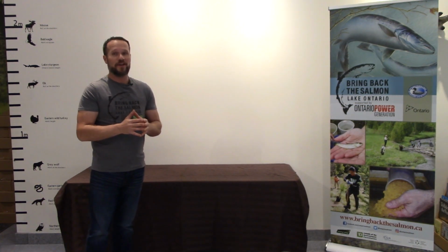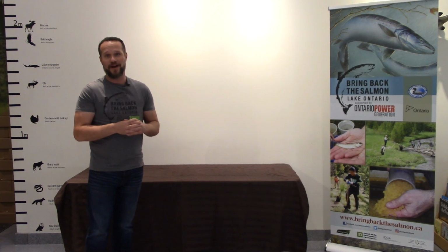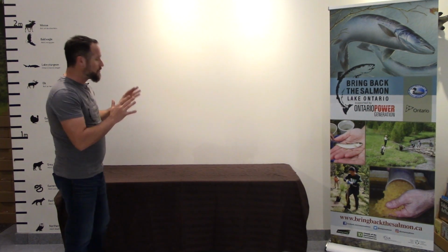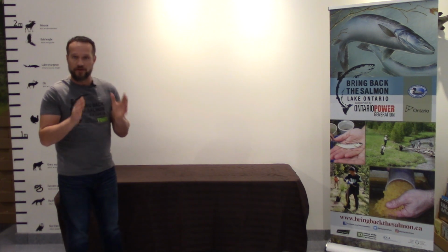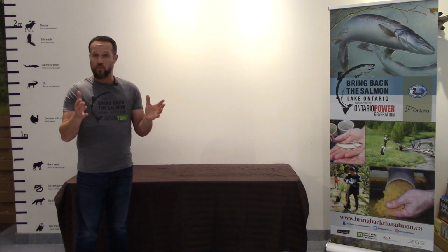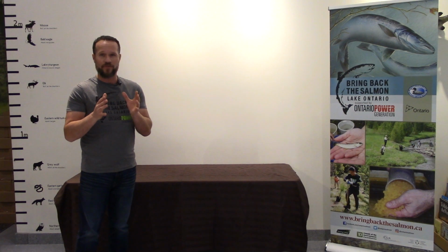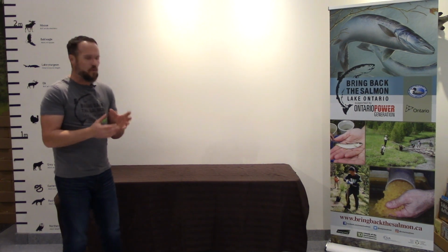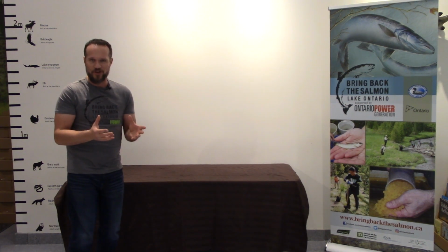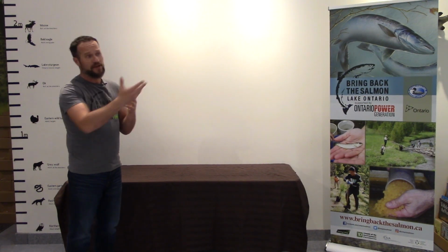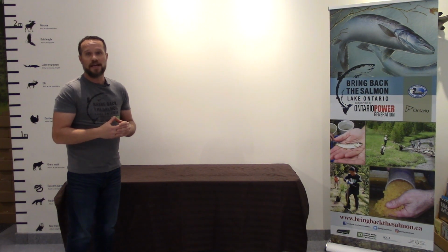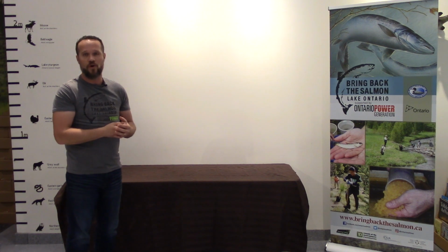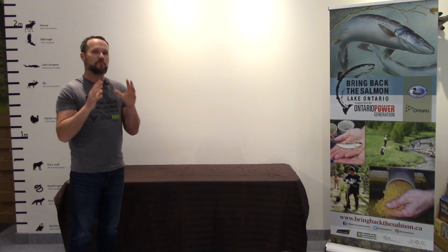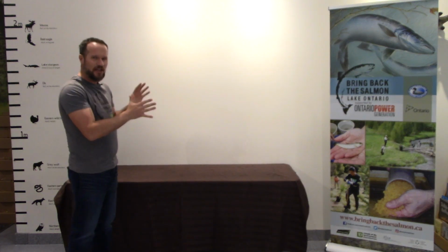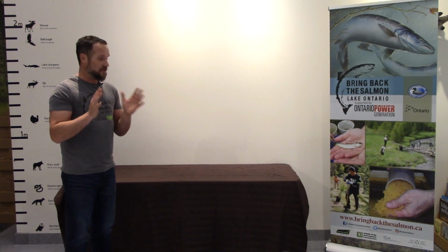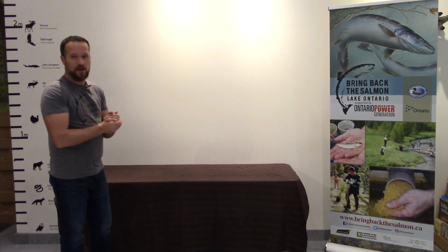First thing we want to think about is where we're going to put our classroom hatchery equipment. We want a spot that is away from any exterior doors, windows, or heat sources. That's just because we want efficiency of the unit. We don't want it being warmed up by sunlight or a heat source while the chiller is trying to cool our water down. We also want stability of temperature, so having it inside, away from those things, is an important consideration for where we're going to put it.